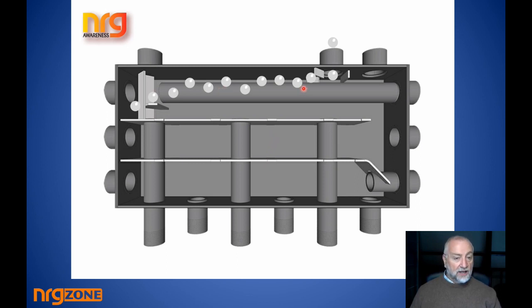But when we're talking about the air, there's more than the fact that the air is traveling here, because in each of the chambers there is a cavity created at the top that actually acts as another vent trap, let's say. So you can see there's one here on the return, there's one here on the bypass, and each of those will catch air. There's a gap where the metal is not welded on the inside. It isn't enough to cause any serious amount of heat to drift through, but it is enough to let minute micro bubbles of air continually pass up until all the air is gone, so that they finally reach the top chamber and are released by the air vent.